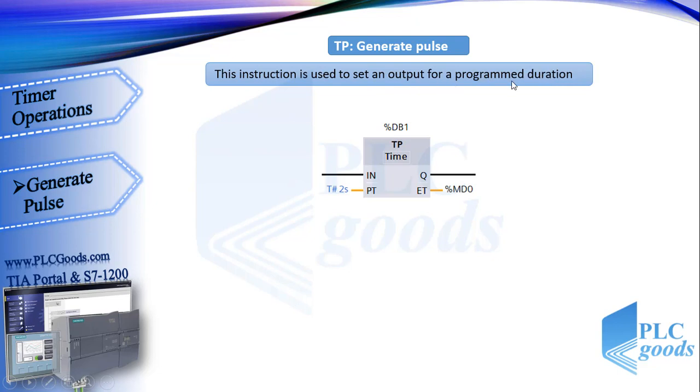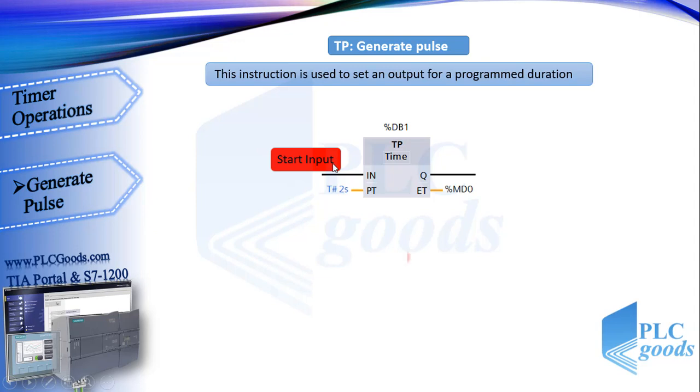Alright, let's start learning timers. This is the ladder symbol of generate pulse timer. This instruction is used to set an output for a programmed duration. Here is its first input. This timer will generate pulse if the RLO at this input changes to one. Generally, this block needs a signal like this to generate a pulse.